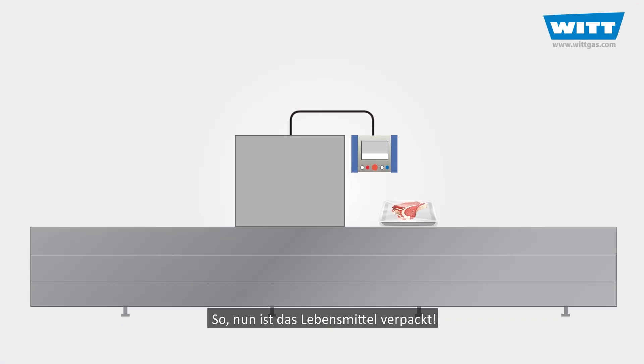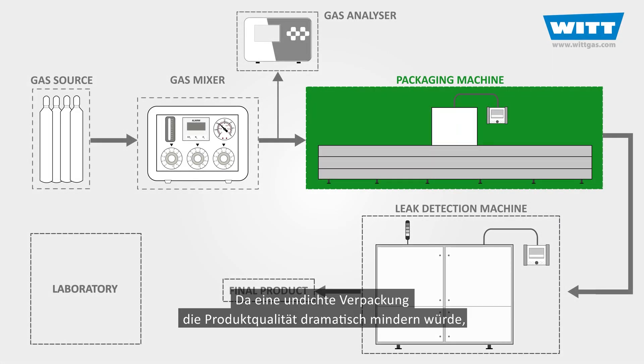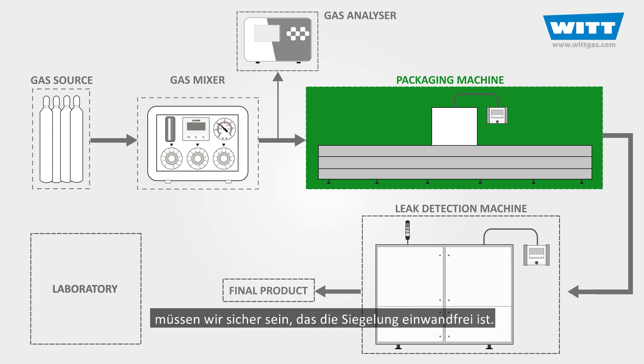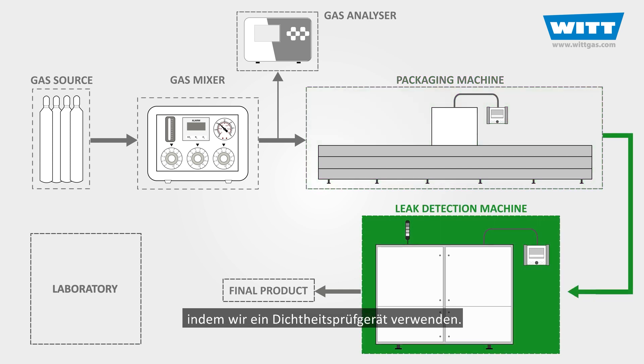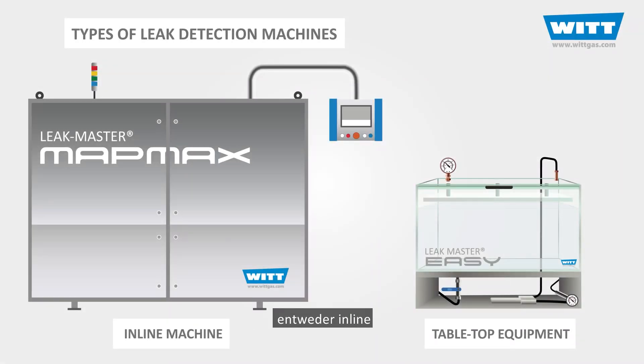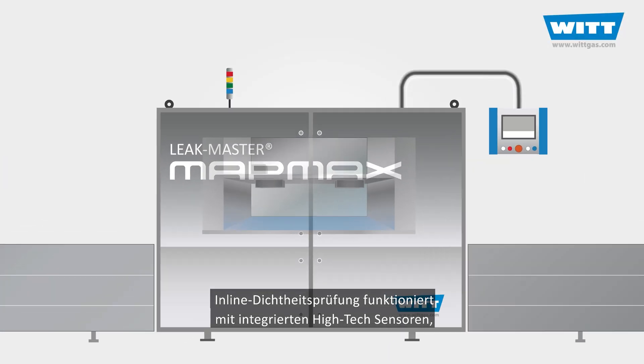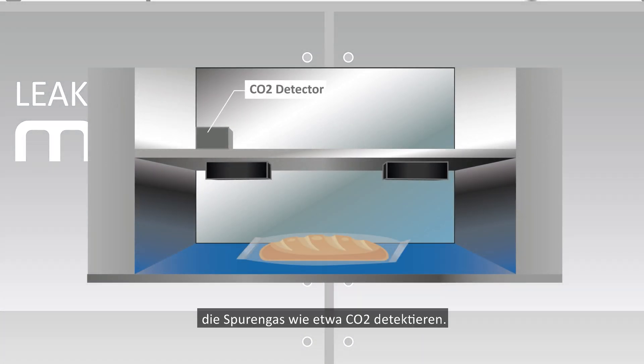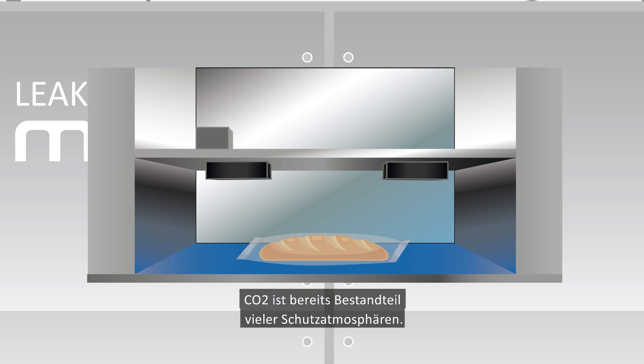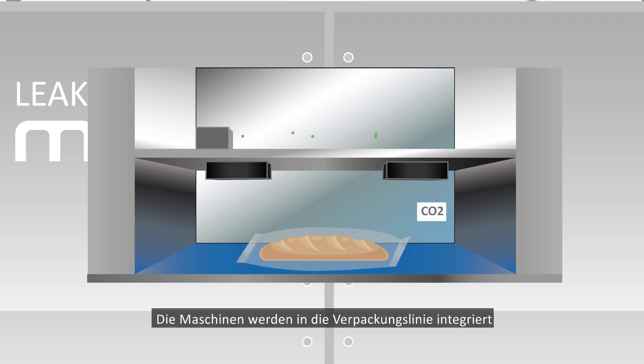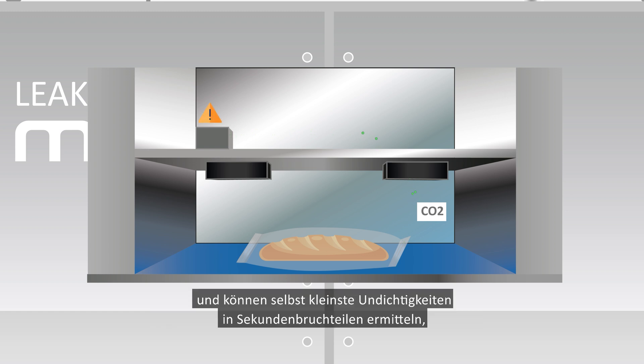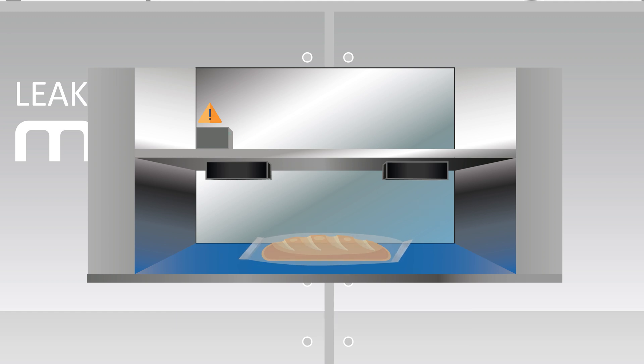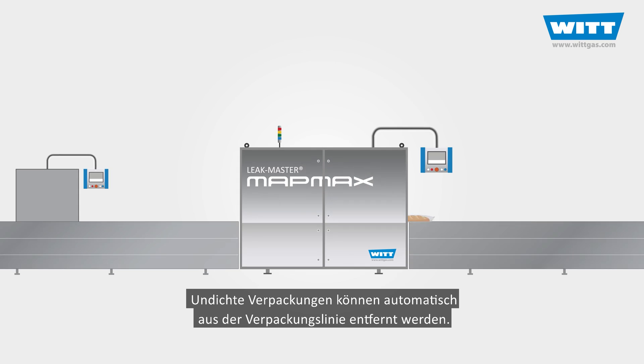Finally, we have our food packed. But as our product quality will be dramatically affected by leakages, we have to be sure it is sealed properly. So the next stage is to make sure the product package is free from any leakages, using a leak detection machine. In-line leak detection machines work with integrated high-technology sensors which detect trace gases like carbon dioxide. CO2 is already part of the modified atmosphere — it delivers the best results in terms of relevant leak size, and it's not expensive. They can detect even the smallest leaks in a fraction of a second when the trace gas escapes from the packages, and can also automatically remove faulty packs from the production line.